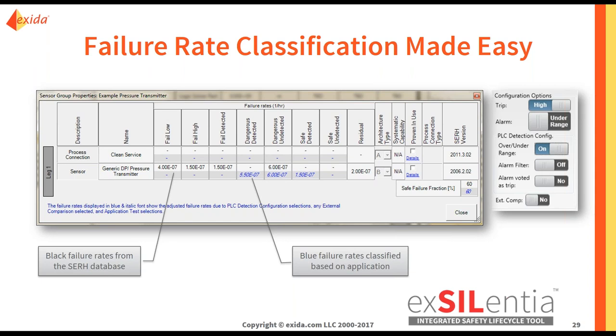Then you see the blue failure rates. These are taking the fail low, fail high, fail detected, etc., and classifying them according to how you configured your system. How does it know? On the other side, you see the configuration options. Here we selected that this would be a high trip, and that if there is an internal transmitter failure, the predefined action is to drive it under range. The PLC detection configuration is that over and under range signals are detected. We don't have any trip delay, and we say that not all alarms are voted as trip. You also see at the bottom we don't have any external comparison. This is our sample problem, showing how the failure rates are classified according to this configuration.